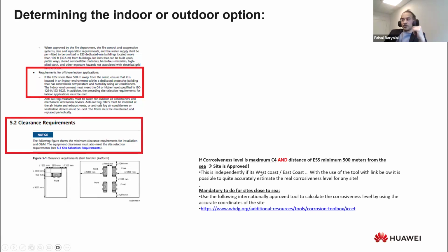And here is the way to do it. There's an international standard platform where we can put in the coordinates of our project, and it will give us the value for the corrosiveness of the air. If it is up to C4, then we can still use the battery outdoors. But if it's above C4, then we have to use indoor installation with good ventilation. This ventilation system is also described in the manual: a mechanical ventilation system, where the filters should be changed periodically, with very efficient air circulation inside the room you're installing it in.